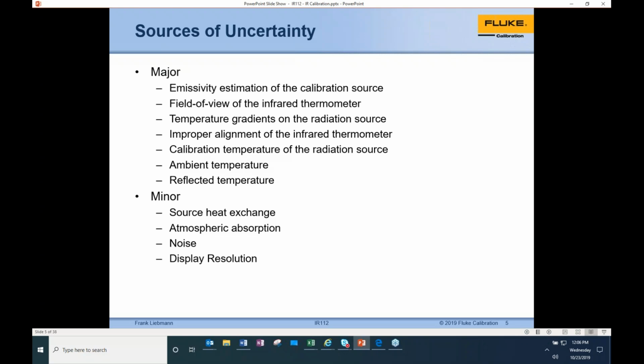Some of the other things to consider is your environment where you're performing the testing. So ambient temperature, typically you want to be in a laboratory type controlled environment. Usually most labs run a typical spec of 23 plus or minus 5. I do know on the mass and dimensional labs, they're usually 21 plus or minus 3. So again, you're wanting to be in a good controlled ambient environment. And then two, we'll talk a little bit more further on this, reflected temperature.